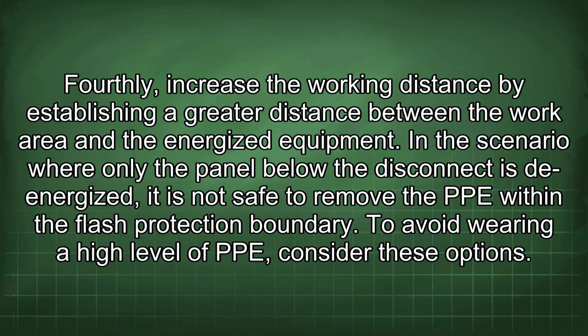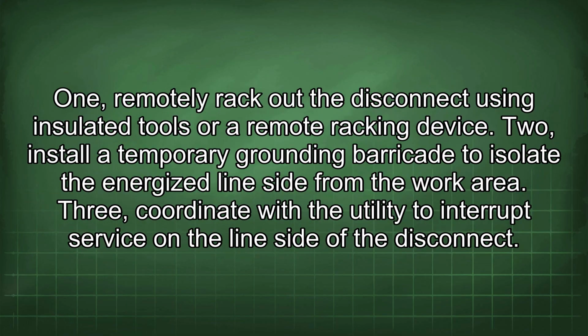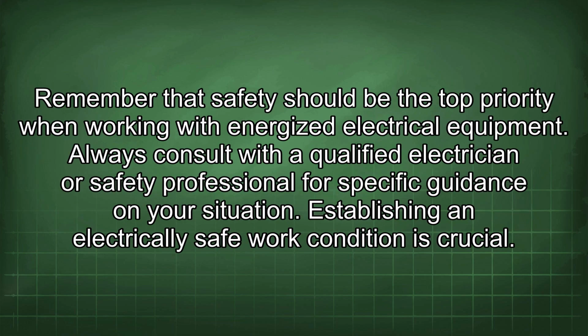To avoid wearing a high level of PPE, consider these options. 1. Remotely rack out the disconnect using insulated tools or a remote racking device. 2. Install a temporary grounding barricade to isolate the energized line side from the work area. 3. Coordinate with the utility to interrupt service on the line side of the disconnect. Remember that safety should be the top priority when working with energized electrical equipment. Always consult with a qualified electrician or safety professional for specific guidance on your situation.